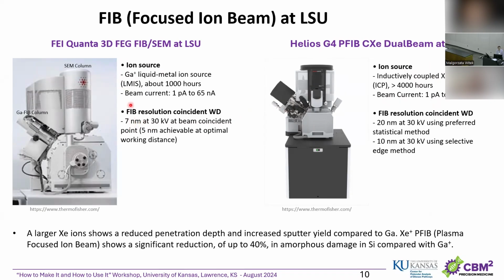What you can see here is that for gallium ion FIB, the smallest structure you can produce is around 7 nanometers. So this is the smallest beam size you can produce using gallium-based FIB. While for xenon-based FIB, the smallest beam size is around 20 nanometers. So you can imagine that with this xenon-based FIB, you cannot really make small structures. However, you can mill very fast. I will show that shortly.